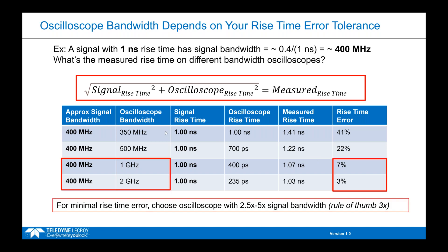At one gigahertz, the measured rise time is 7% slower than the signal's actual rise time. And at two gigahertz, that error drops to 3%. The takeaway is that when you have an oscilloscope with bandwidth at least two and a half times your signal's bandwidth, you're really starting to minimize your rise time error. If your error tolerance is even tighter, you would want an oscilloscope with five, six, or even seven times your signal's bandwidth — it really depends on your error tolerances.